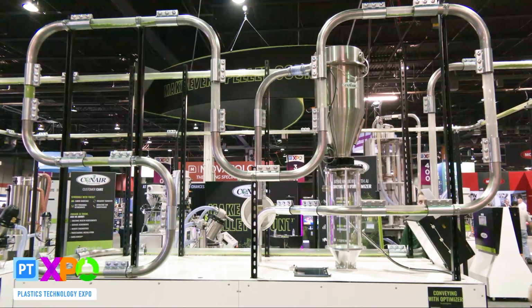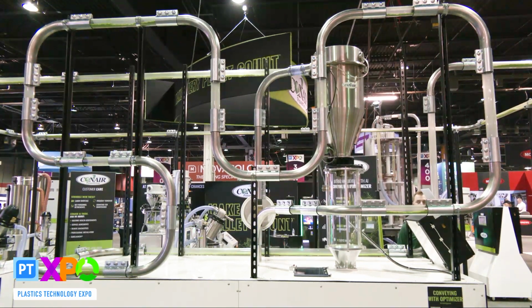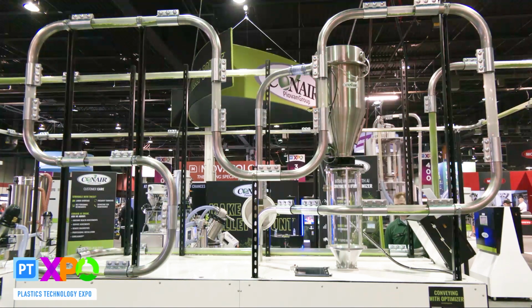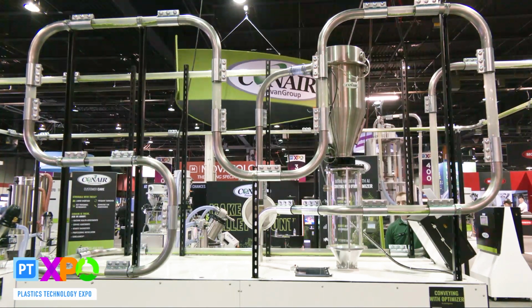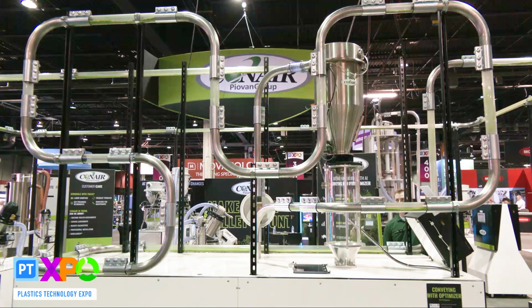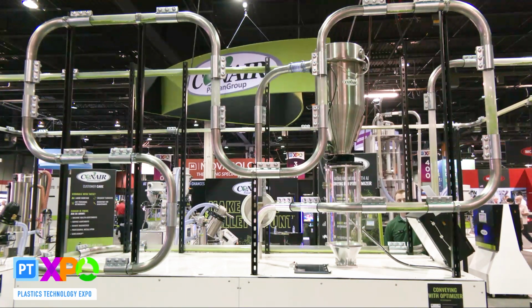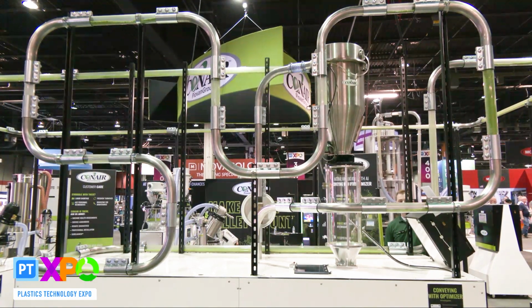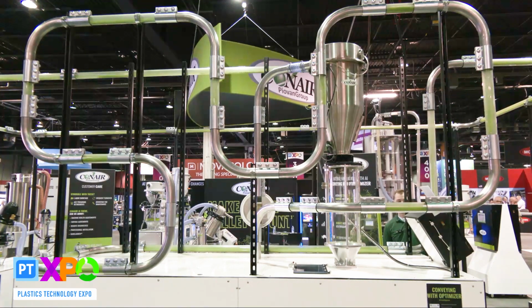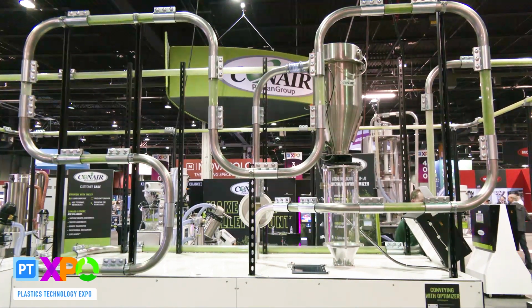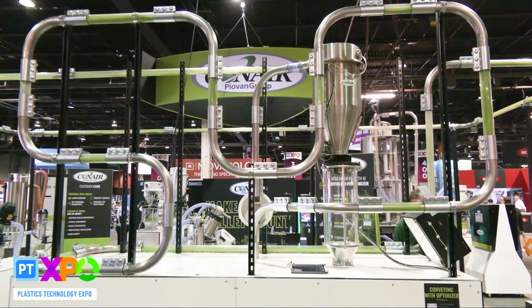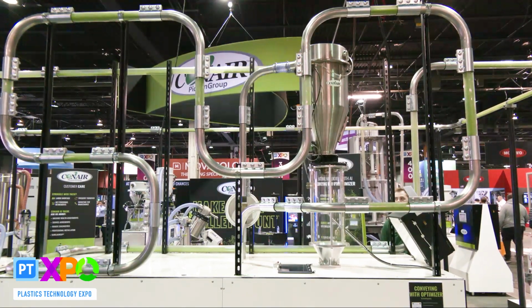Instead of having that plug or that clog somewhere that now we've got to go hunt down, find where it's at and start taking stuff apart, we're going to now induce more airflow into the system and move this all through and get us back to that 8.5 inches of mercury that we wanted. So this is our most recent advancement.